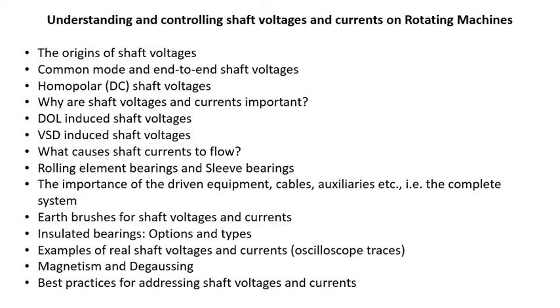What causes shaft currents to flow? So just to take a step back and look at it to give an understanding, because sometimes the current flow is quite complex. I mean, it's complex even in yours just showing just the motor. And when you get to the cables and everything else, it actually can be a lot more complex. Then I'll look at the difference between rolling element bearings and sleeve bearings.